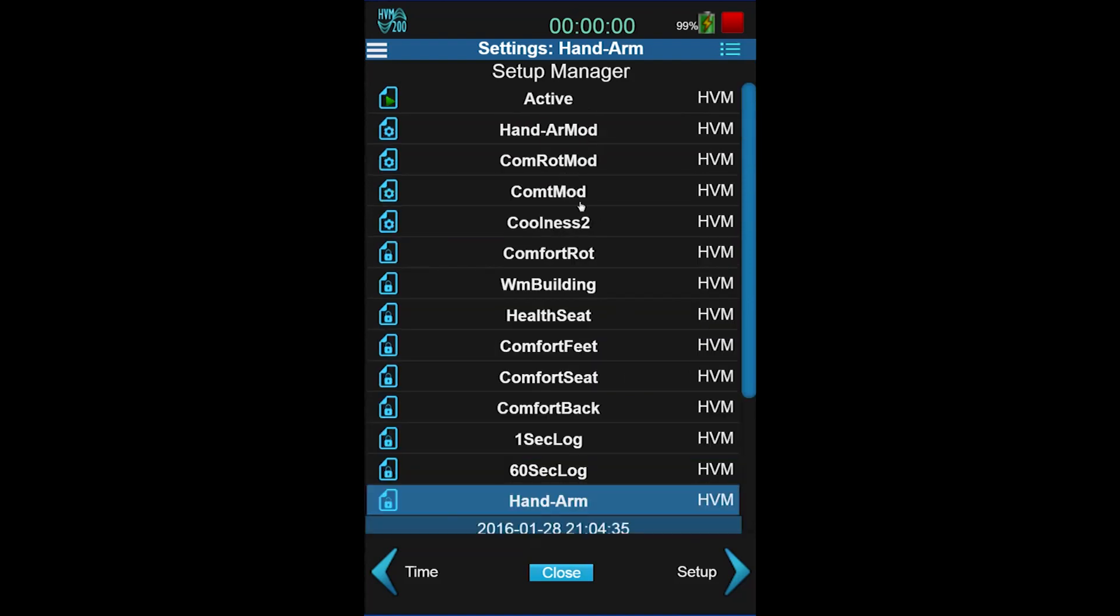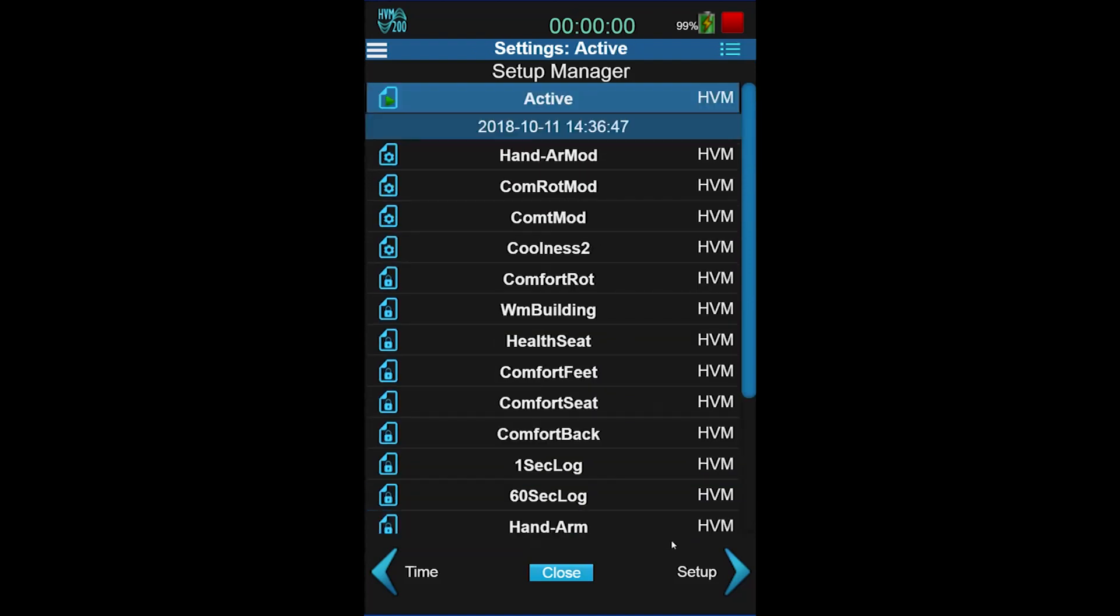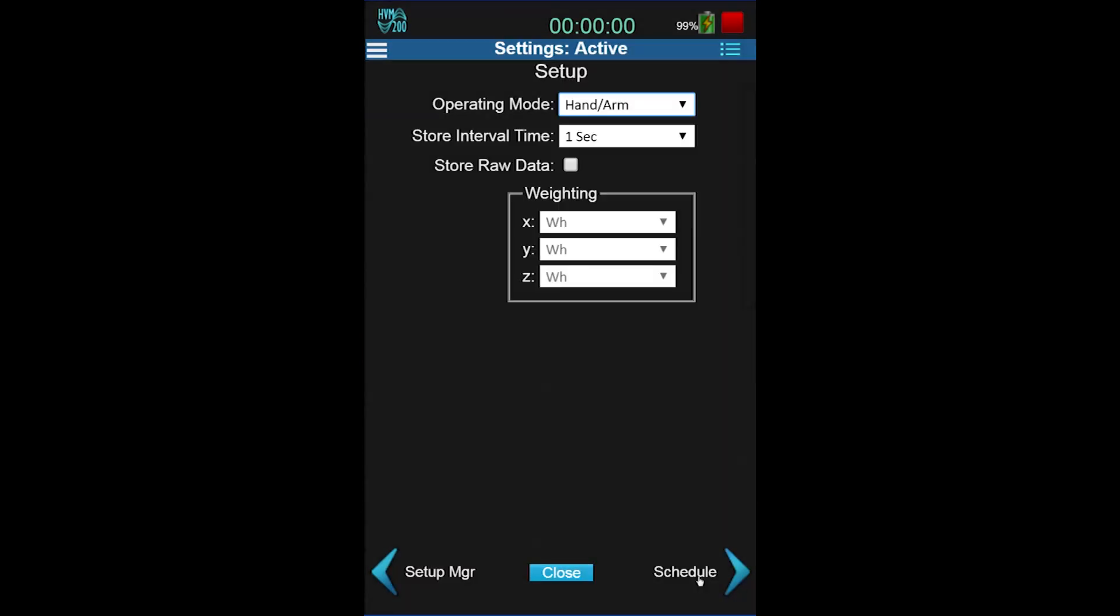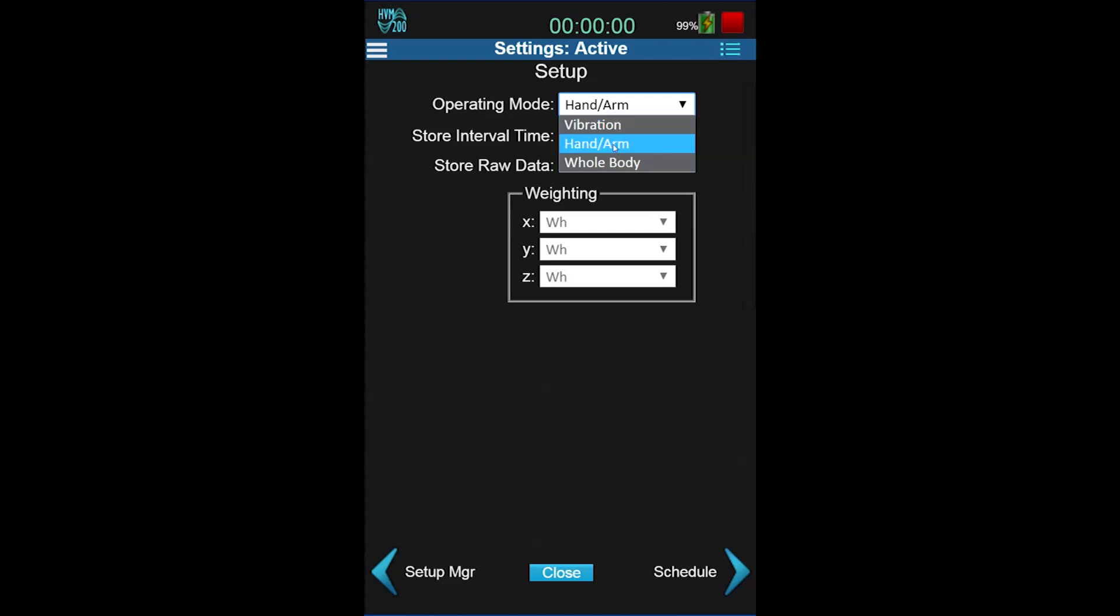Now in the active setup, navigate to the right using the bottom arrow. There are three options for Operation Mode: Vibration, Hand Arm, and Whole Body. Vibration is for general vibrations across frequencies. Hand Arm and Whole Body add weightings from the standard for those measurement types.